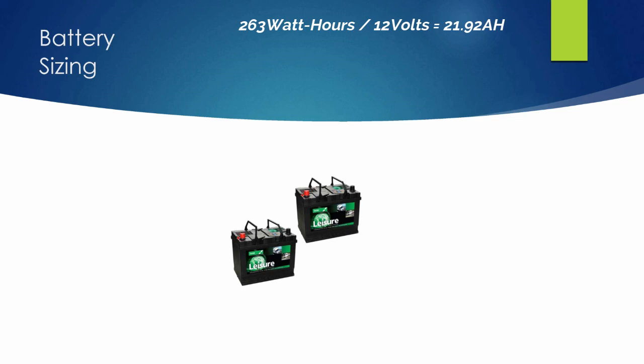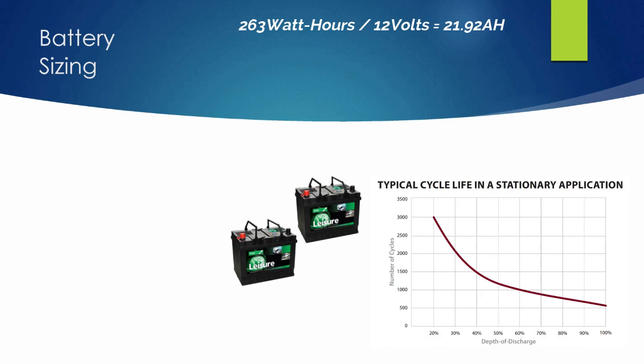Lead acid batteries don't like to be discharged entirely — at best you don't want to go further than 50% discharge. AGM batteries can go up to 80% discharge, but the deeper you discharge the battery the fewer charge cycles you'll get out of it. It's far better to keep the depth of discharge to a minimum for a much longer battery life. In this example we'll use 50% depth of discharge, so we take 21.92 amp hours divided by 50%, which effectively doubles it to 43.84 amp hours.